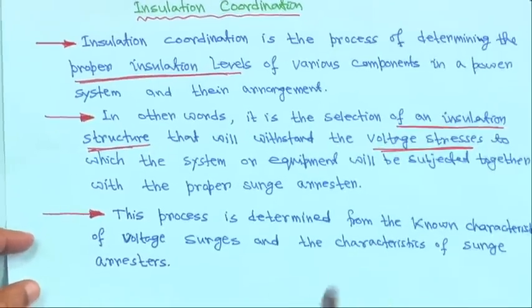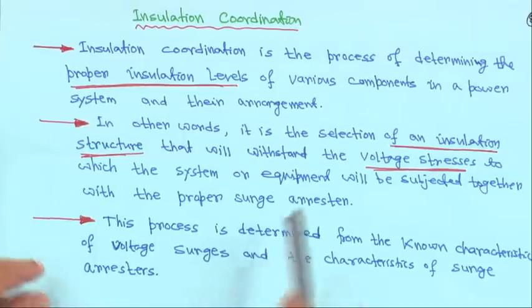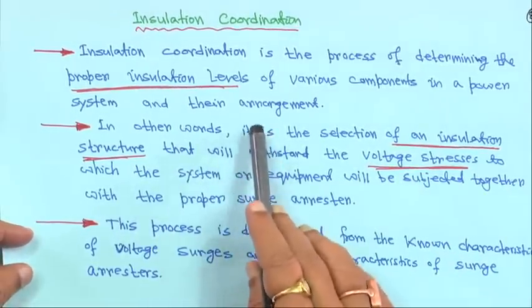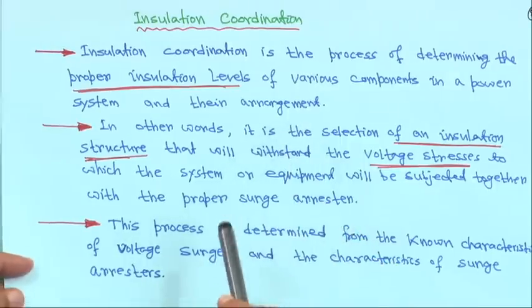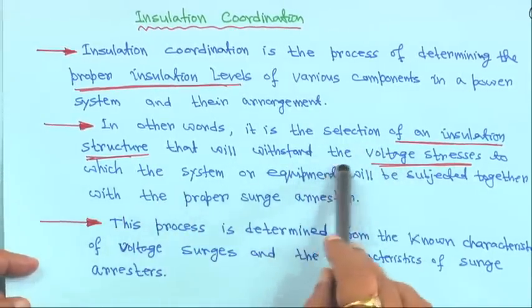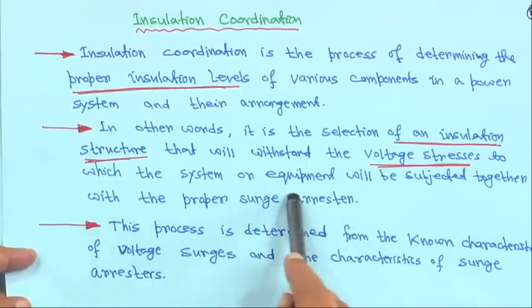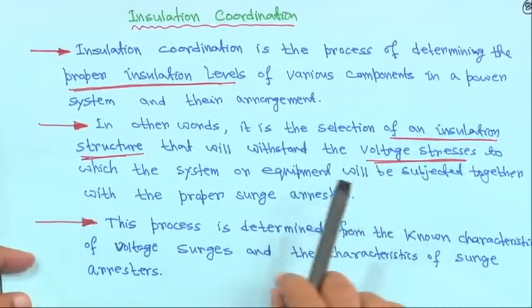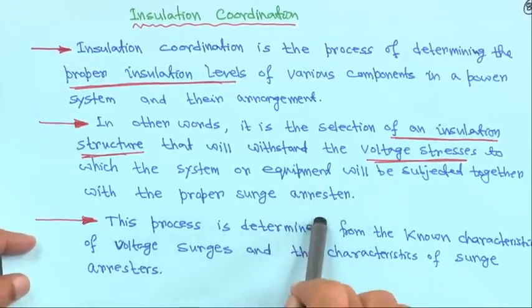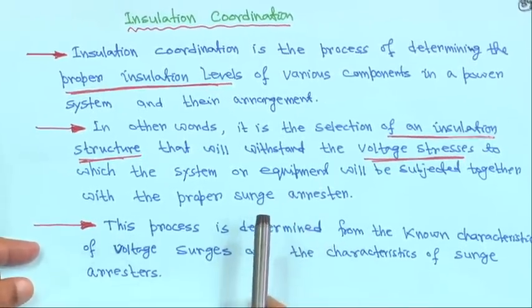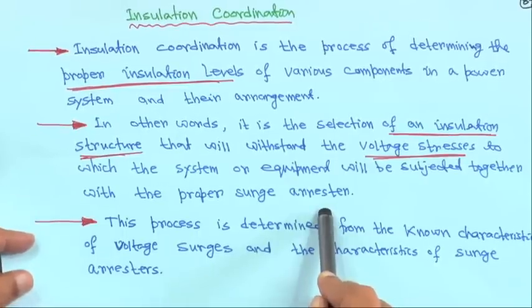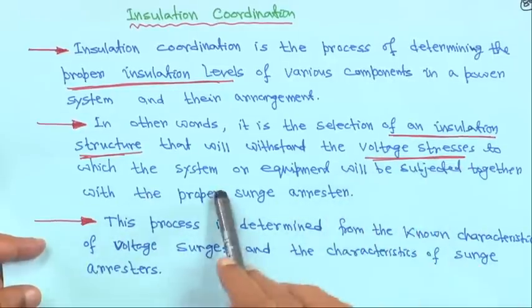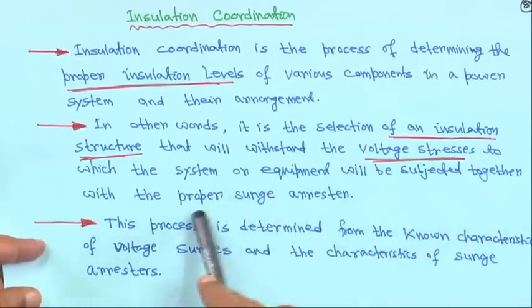Insulation coordination is the process of determining the proper insulation level of various components in a power system and their arrangement. In other words, it is the selection of an insulation structure that will withstand the voltage stresses to which the system or equipment will be subjected, together with the proper surge arrestor.